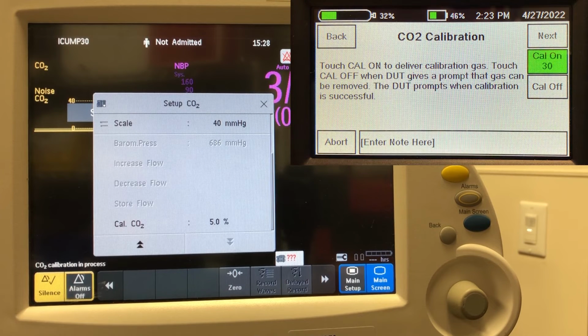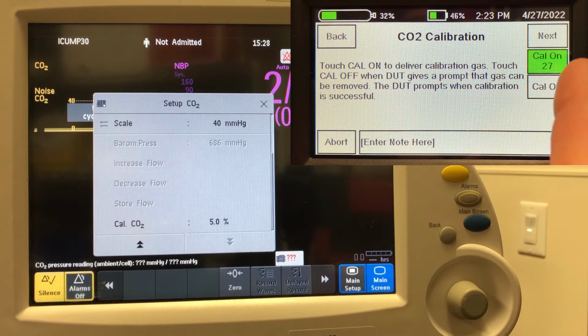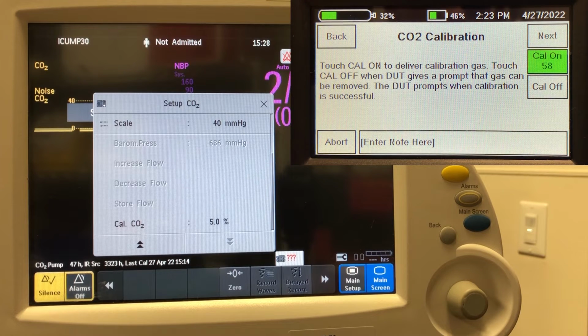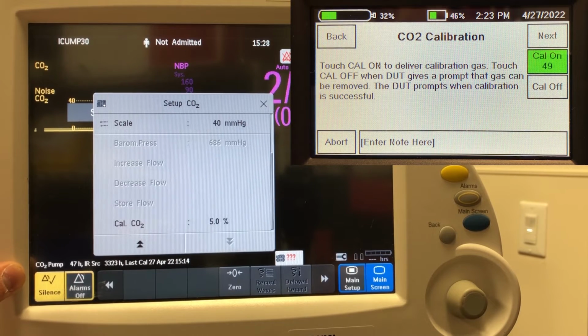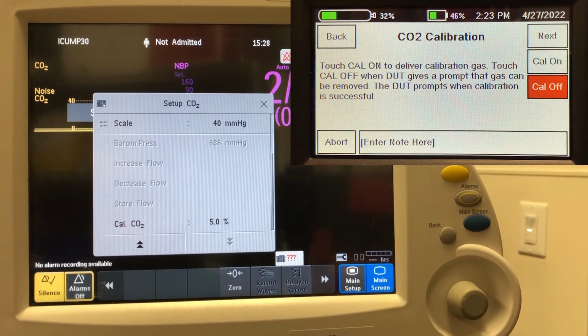You'll notice too it has a countdown. If the device you're testing needs more time, you just touch that again and it resets the timer. If that timer runs out, then it just turns the cal gas off. It's a means to prevent loss of cal gas. So you can see over here it's telling us to remove cal gas. Right there, remove gas, so we can turn it off. And then we wait for the monitor to complete its calibration calculations. Right now it's saying calculating, but eventually it will say calibrated on and give a date. When it does that, it's done and the calibration's accepted. There it is, calibration done. Okay, so we can say next.